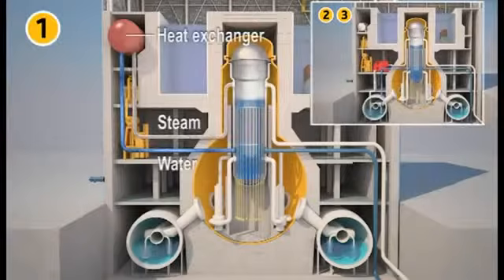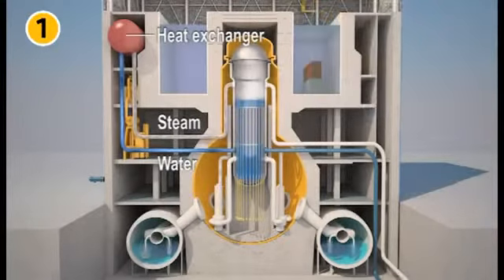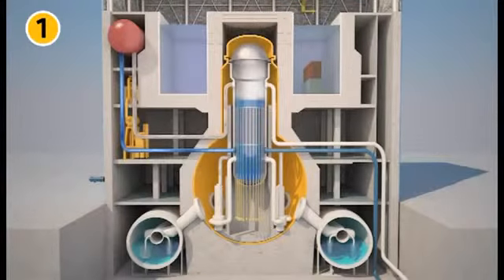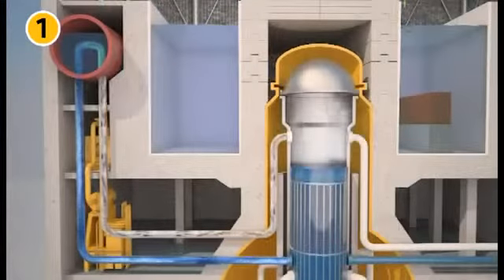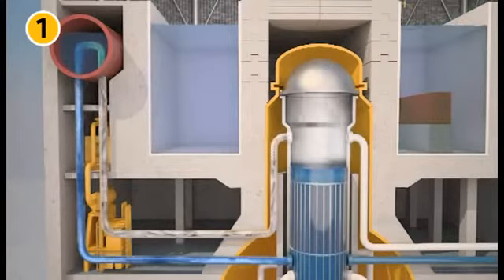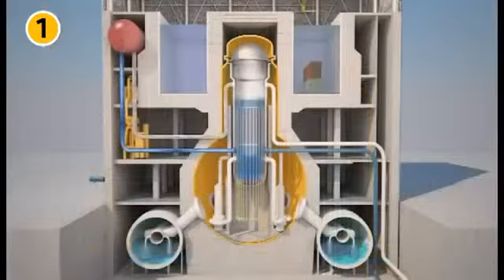In reactor 1, there was no turbopump, but a heat exchanger, which condensed steam from the reactor vessel. The condensed water was reintroduced into the reactor vessel by gravity. This heat exchanger provided core cooling by natural convection for more than 10 hours. Until then, everything seemed under control.